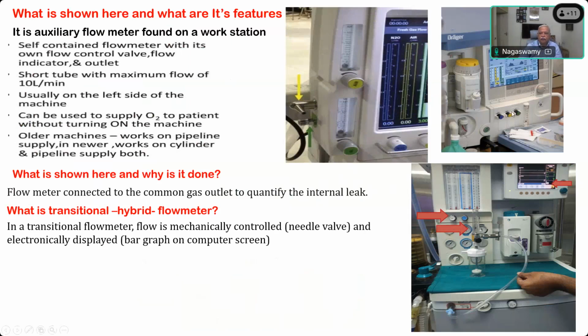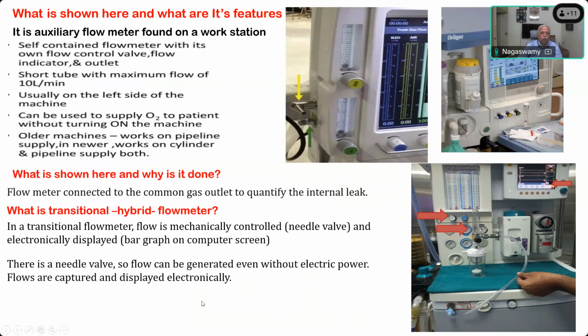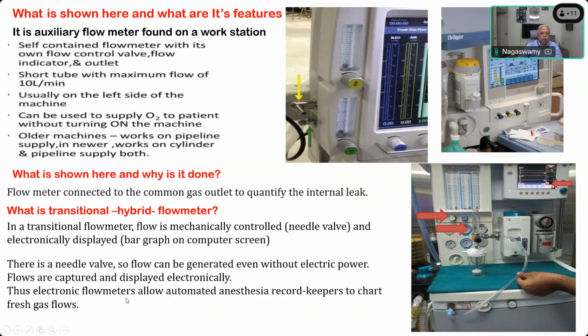You can see this is the control knob for the needle valve, and you get the bar graphs for the display. Instead of the tube with the bobbin, you get the display in electronic form. There is a needle valve, so flow can be generated even without electric power, and flows are captured and displayed electronically. Thus, electronic flow meters allow automated anesthesia record keepers to chart fresh gas flows. That is the idea of having a hybrid flow meter.